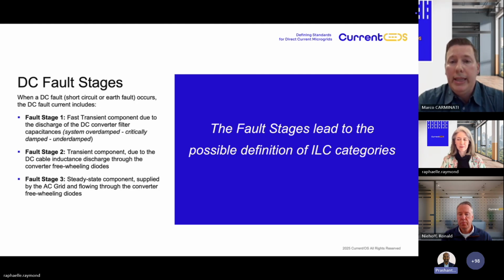According to the ratio between the DC capacitances and the inductances, we can have that the system is overdamped, critically damped, or underdamped. In particular, if the system is overdamped or critically damped, basically we have that the discharging current waveform is not oscillating. So basically we don't have the fault stage 2, but we move directly to the fault stage 3. We can reach a very huge current peak due to the DC capacitor discharge, but we don't have the fault stage 2.